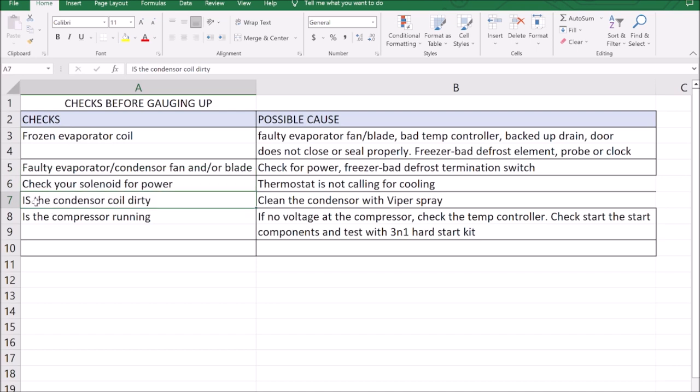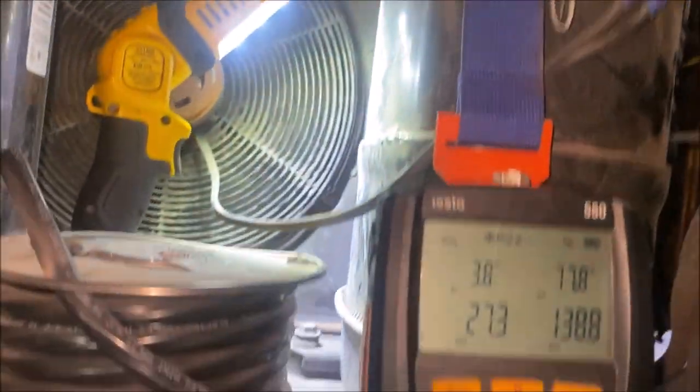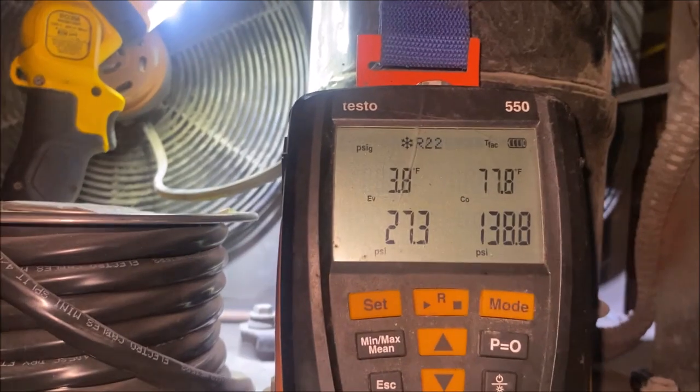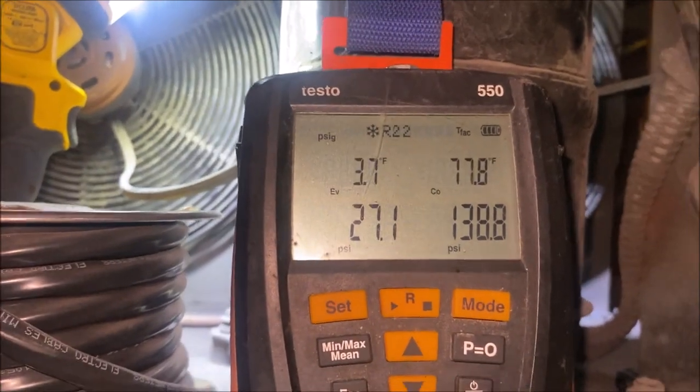Let's move on to the next items now which is: is the condenser coil dirty and is the compressor running? So let's hop up here. Our condenser coil, it's a little bit dirty but not enough to have our temperature at 52 Fahrenheit but we'll get that cleaned. Our two fans are running. So next thing would be to check the sight glass and look at that, we do not have a sight glass. So guess what? We're going to have to gauge up.